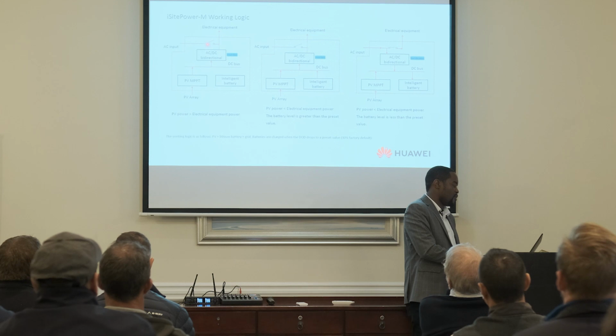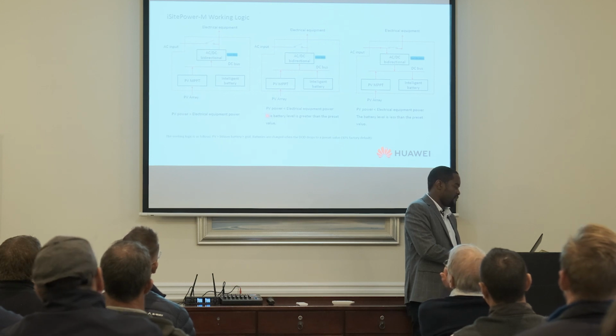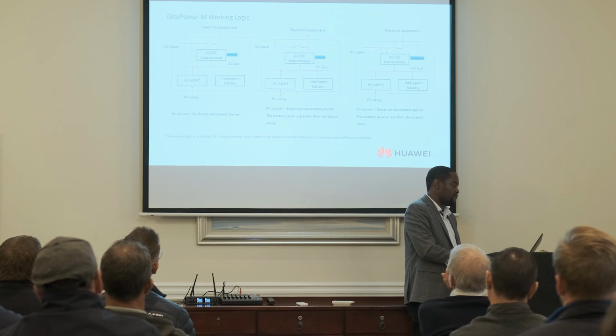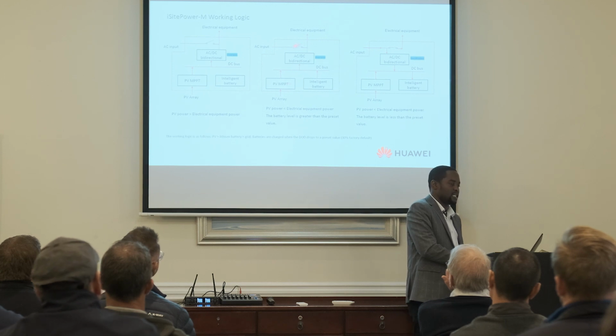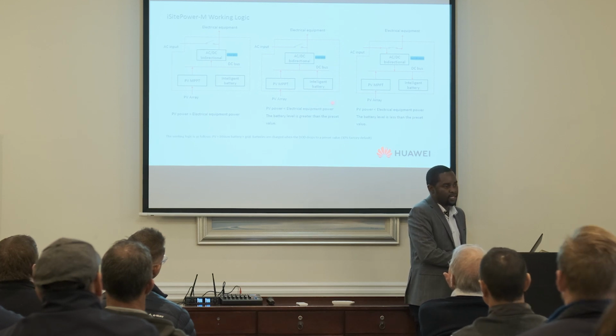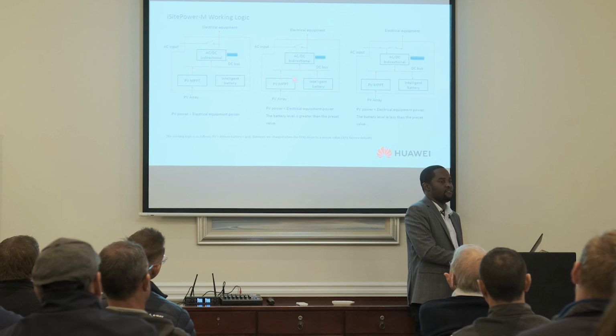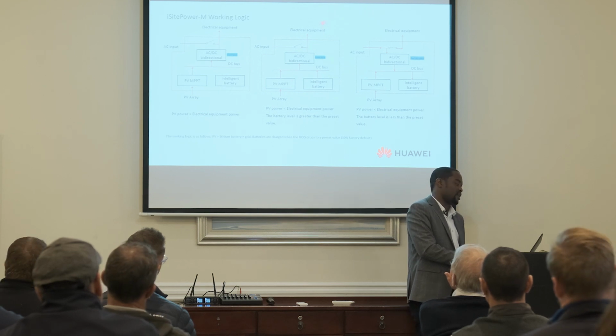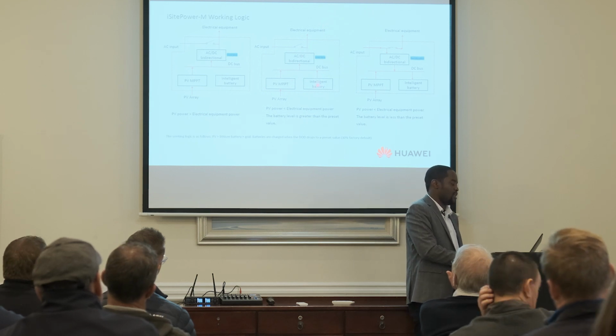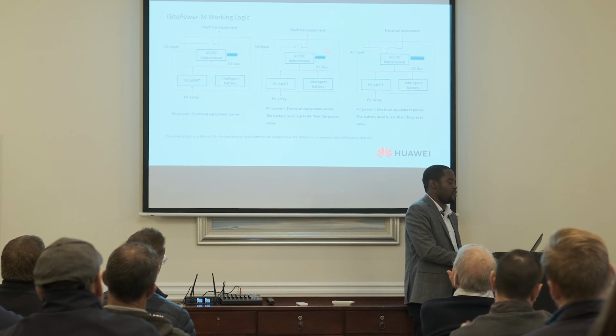Then the other scenario is when this is not enough. When the power that you are producing from your PV array is not enough to meet the load demands, then you need a second source of power. Instead of taking from Eskom and increasing your Eskom bill, you look at your batteries first. That's the intelligent battery system. Am I higher than the reserve SOC? If I'm higher, then I can safely discharge and help the PV supply the loads. But if it's lower, then you are taking from your AC, from your grid.